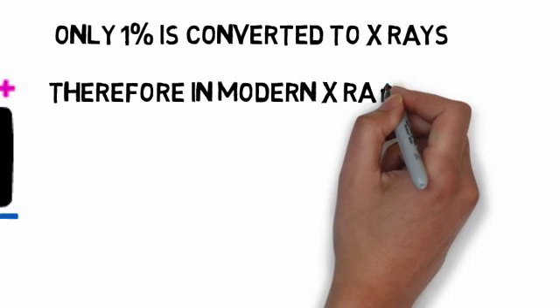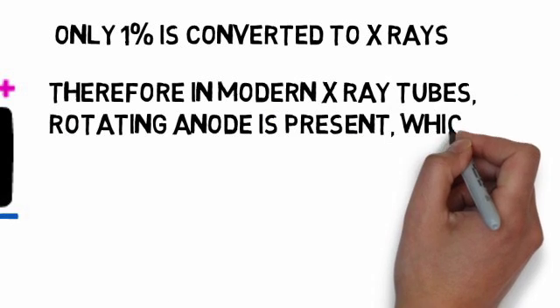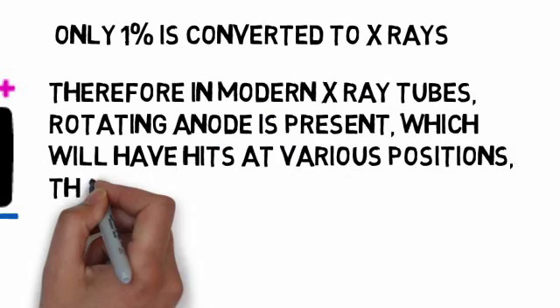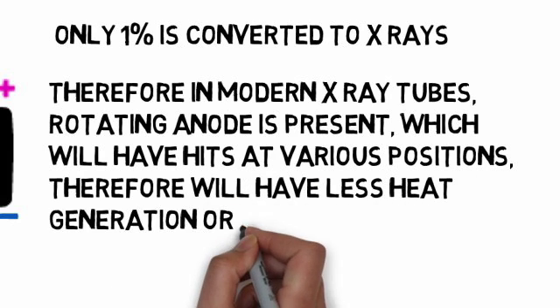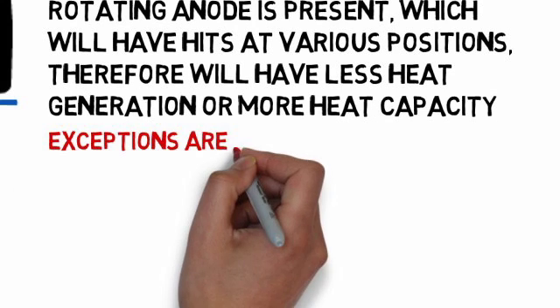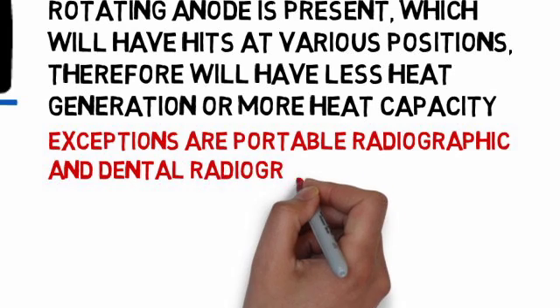Therefore, in modern X-ray tubes, rotating anode is present which will have hits at various positions. Therefore, it will have less heat generation or more heat capacity. Exceptions are portable radiographic and dental X-rays.